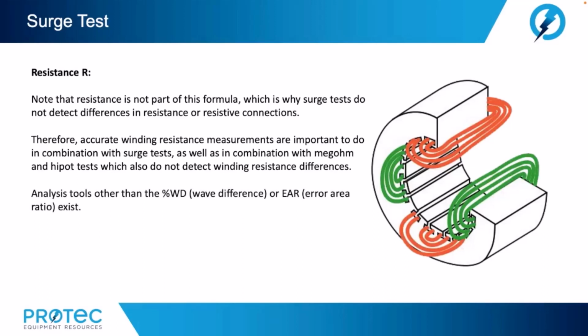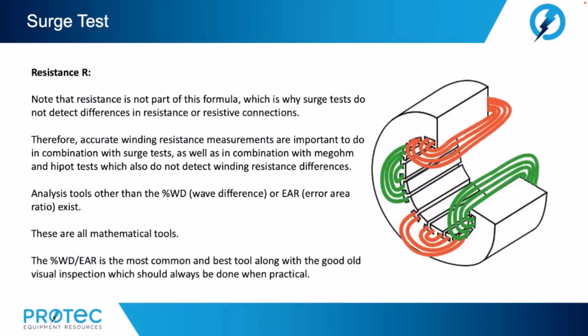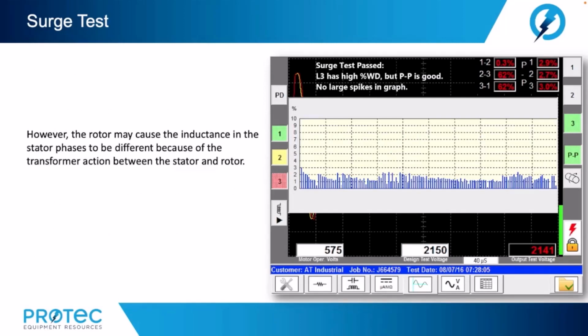Analysis tools other than the %WD, waveform difference, or EAR, error area ratio, exist. These all are mathematical tools. The %WD or EAR is the most common and best tool, along with the good old visual inspection, which should always be done when practical. However, the rotor may cause the inductance in the stator phases to be different because of the transformer action between the stator and rotor. To address these situations, the pulse-to-pulse surge test was designed.